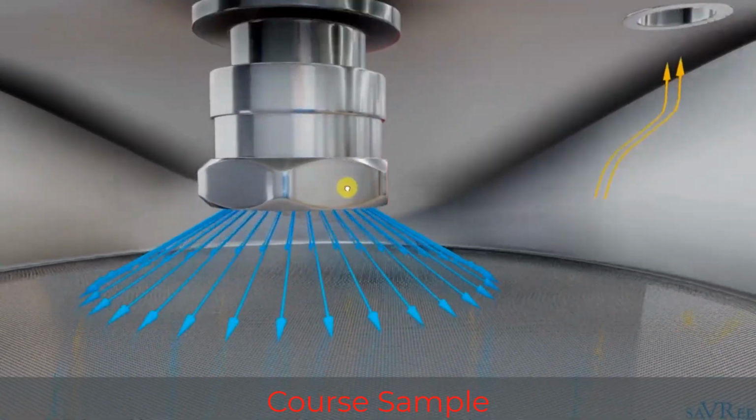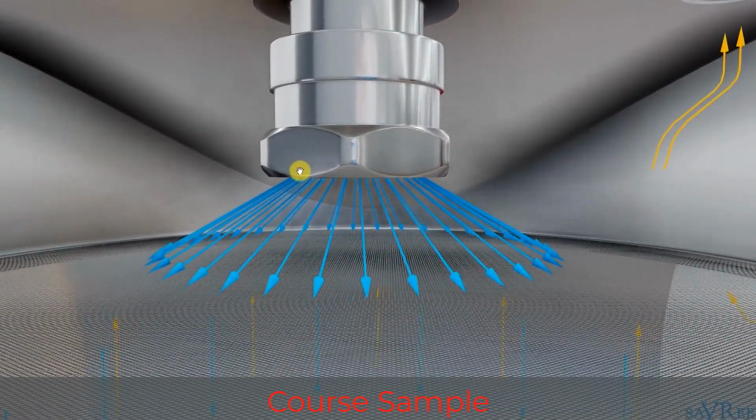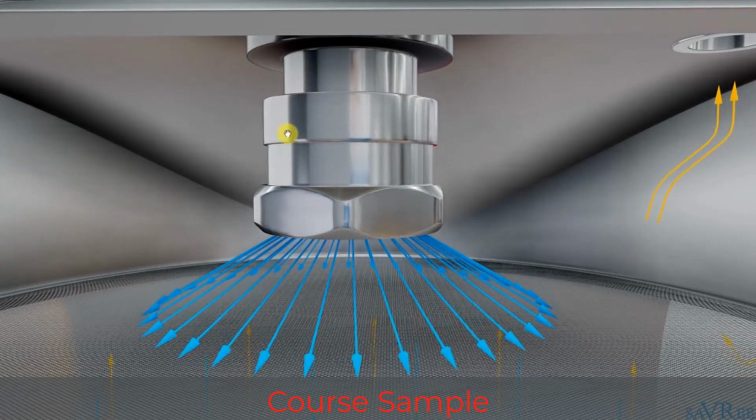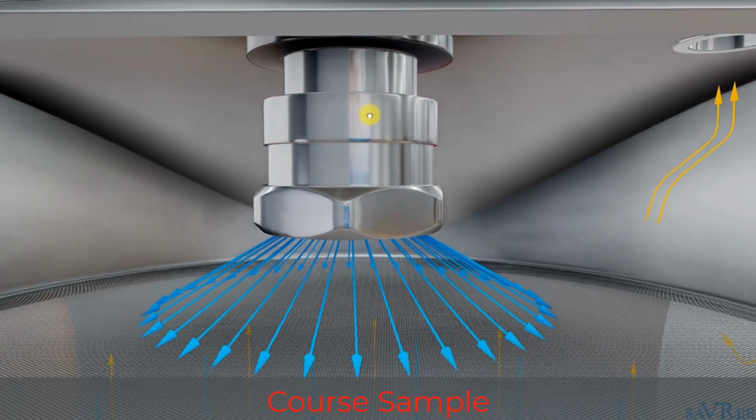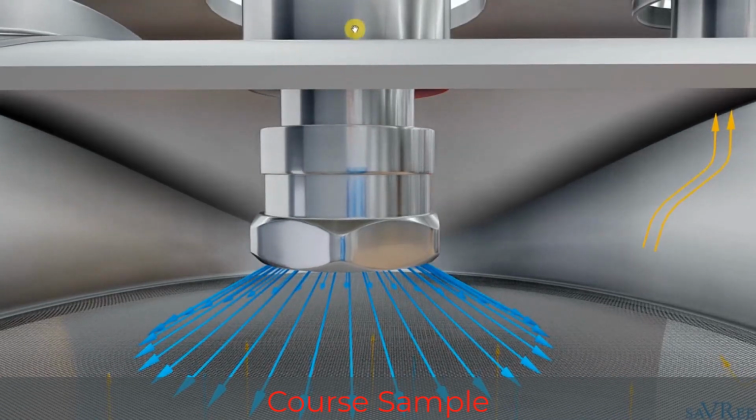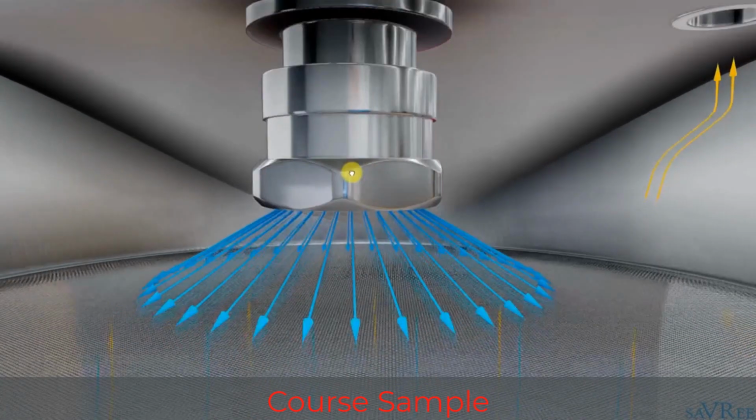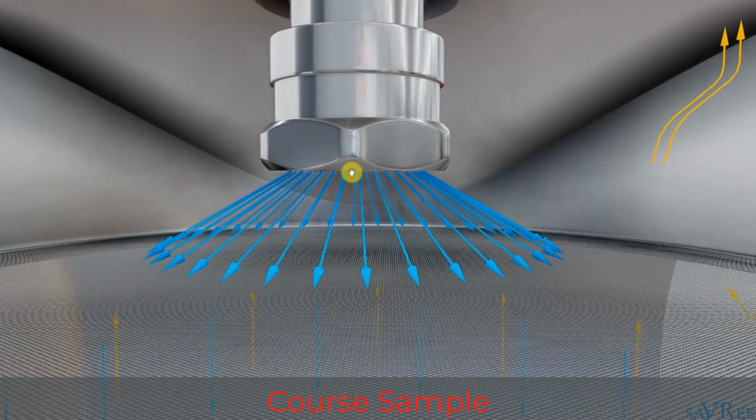If we zoom in, you can see it comes out of a spray nozzle. The spray nozzle will be a spring-loaded spray nozzle, normally manufactured from stainless steel. As the water enters a water box around here, or sometimes slightly higher up, perhaps this section here, the pressure inside the water box will increase. It will overcome the spring pressure of the valve, and the water will spray out of this spray nozzle.